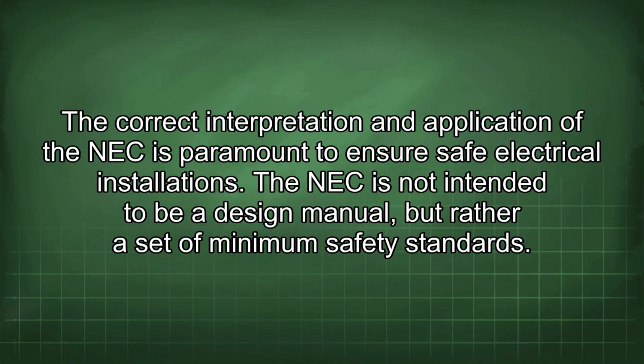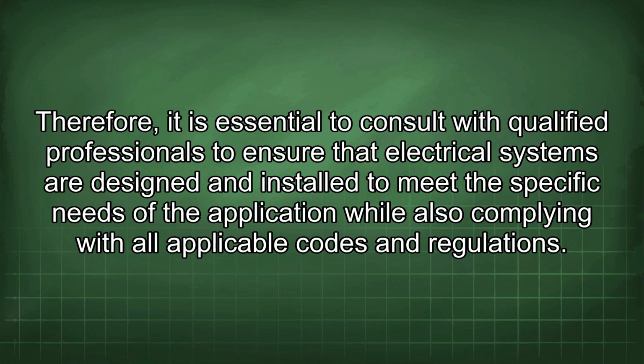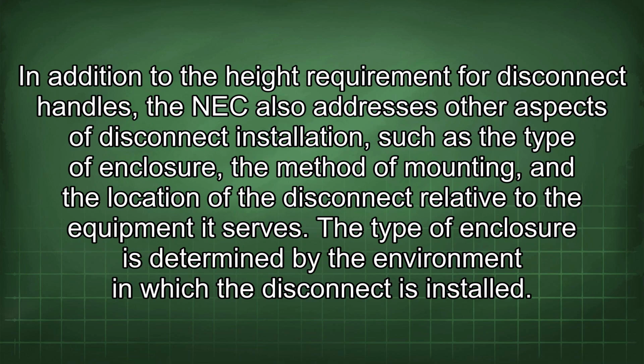The correct interpretation and application of the NEC is paramount to ensure safe electrical installations. The NEC is not intended to be a design manual, but rather a set of minimum safety standards. Therefore, it is essential to consult with qualified professionals to ensure that electrical systems are designed and installed to meet the specific needs of the application while also complying with all applicable codes and regulations. In addition to the height requirement for disconnect handles, the NEC also addresses other aspects of disconnect installation, such as the type of enclosure, the method of mounting, and the location of the disconnect relative to the equipment it serves.